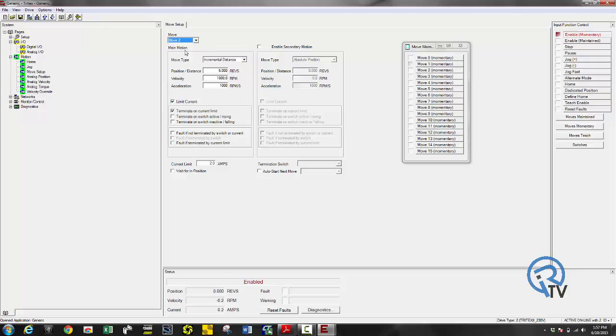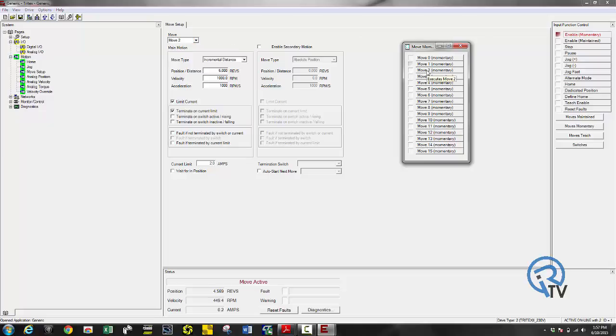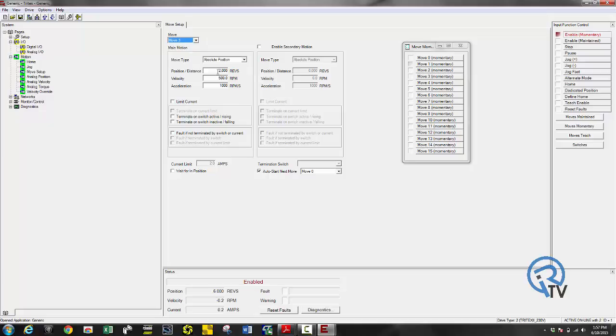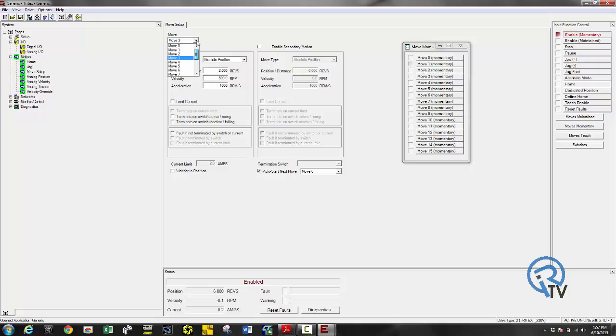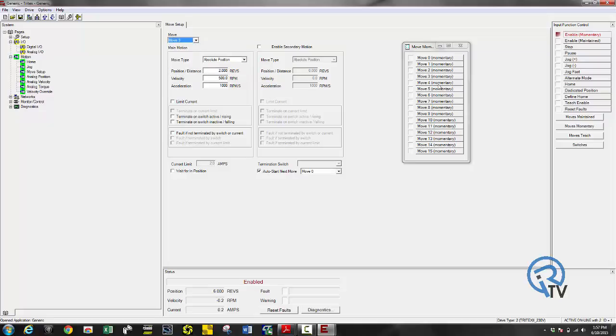Move two should go six revs and if I have something to stop this it would limit out on current. Move three should go out to absolute position of two revs and then back to move zero, which is absolute position of five revs. It's that simple.